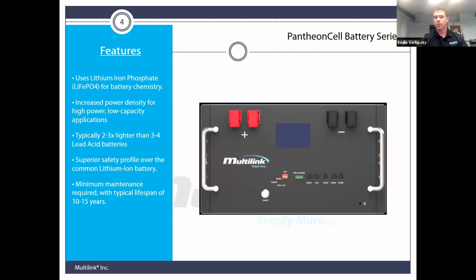With the PantheonCell battery, we typically see between 2 and 3 times less weight compared to lead acid batteries. Our typical lead acid battery might weigh between 70 to 75 pounds, and with 3 to 4 of them, the weight adds up quickly. With the PantheonCell's lithium iron phosphate chemistry, we're able to shave that weight off, become more power dense, and pack much more into a smaller container. The most high capacity battery we have typically weighs around 90 pounds.